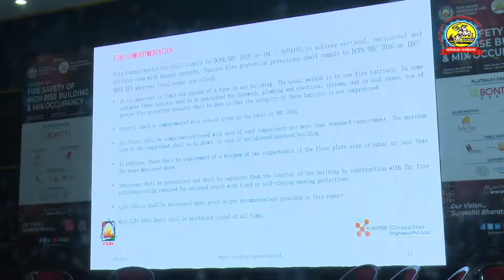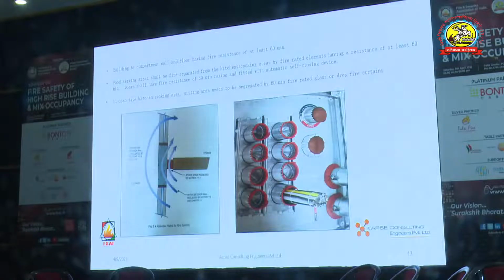Compartmentation is one major aspect, where how do you define your compartment? So if the floor is a slab of 2 hours, every floor is a compartment. You cannot have anything transferring between the floors. I've seen between 2 floors they give an open stair without compartmentation, which is not allowed. If a floor is defined as a zone and a compartment, the floor has to be compartmented between floor and floor. You cannot put an open staircase cut out between 2 floors, because fire from a floor can go above. So compartmentation is one major aspect.